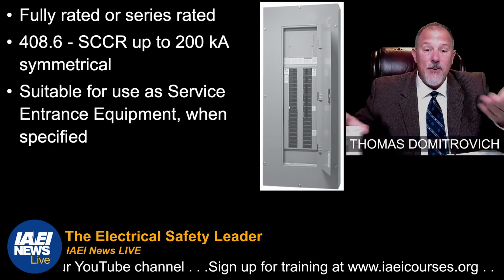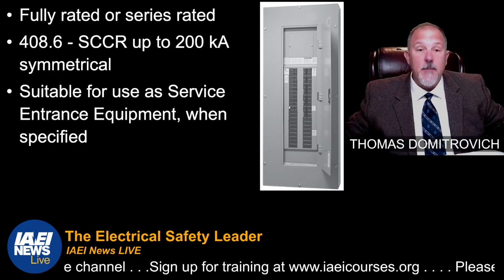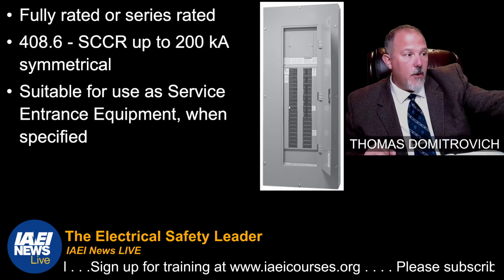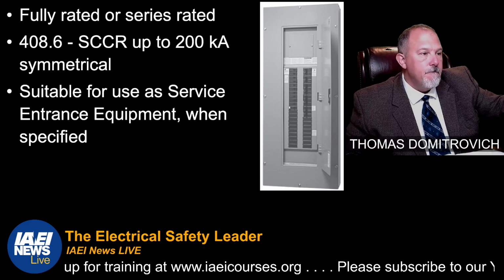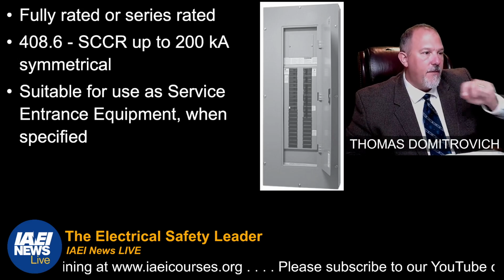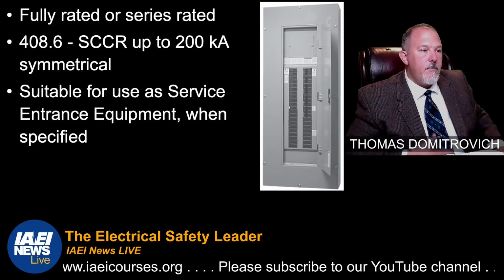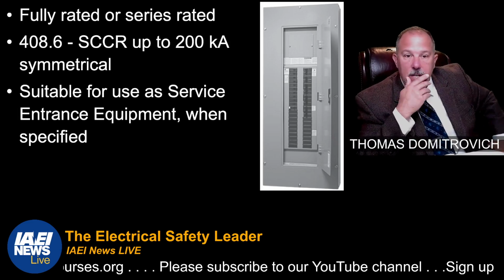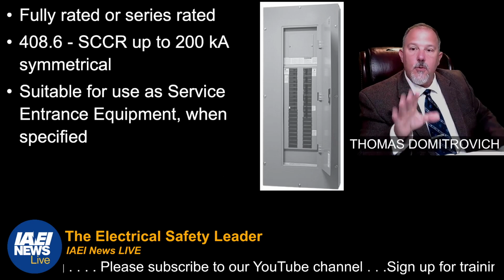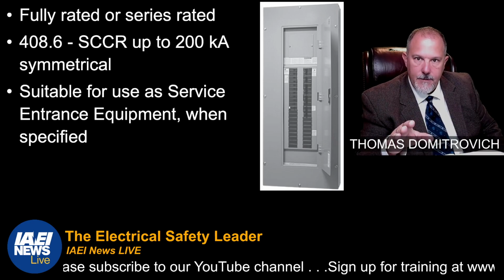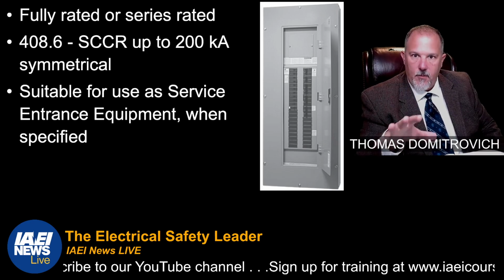I said we'll get to it, and look, it was the next slide. I wanted to talk about short circuit current rating. So this 408.38 talks about being evaluated for the application less than 10,000 amps. So you can get the short circuit current rating of a panel board.